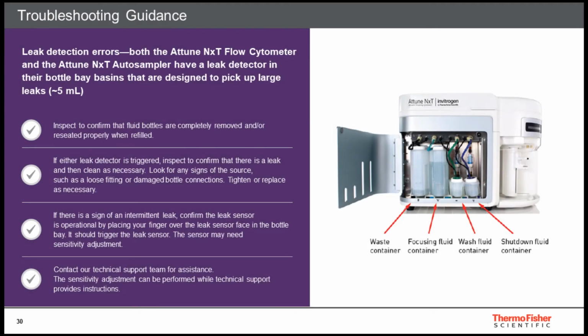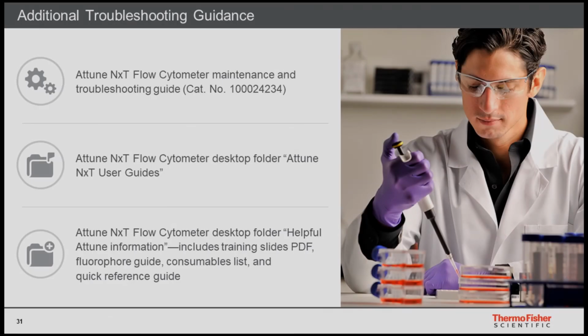The Attune NxT and Autosampler have leak sensors that are conductivity-based and will trigger in the presence of fluid or salt on the instrument floor. In case of accidental leaks, please clean up the bottom of the tray and identify the source of the leak. In case the sensor is constantly triggering without the presence of liquid, please initiate a service call to have an engineer come in to reduce the sensitivity of the sensor. In case of other errors, please consult the Maintenance and Troubleshooting Guide, the Attune NxT User's Guide, or other guides available. Most of the information can be obtained from Thermo Fisher's website.